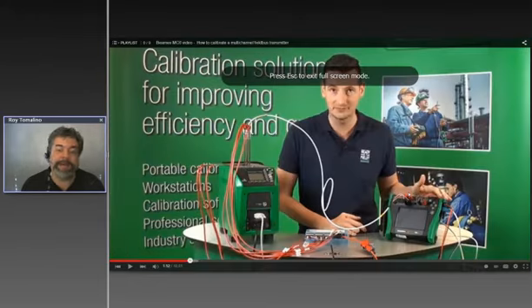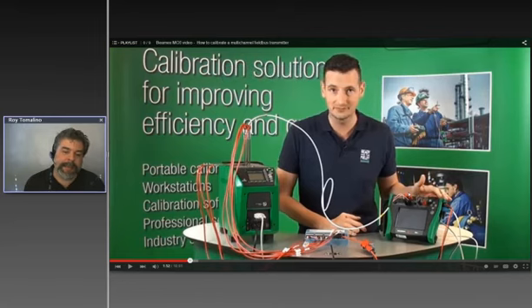And you could do this yourself with, if it were a multi-channel HART, it doesn't matter if it's field bus or not. And we have 8 different temperature sensors plugged into that dry block at one time. So we had a special insert created, and we drilled 8 identical holes so we could have them all in. So when we go to our first temperature, we have 8 different tests or 8 different functions, and we can grab them all individually. So we grab test probe 1 at the first temperature, then we grab test probe 2, and just go around in a circle until we've grabbed them all.